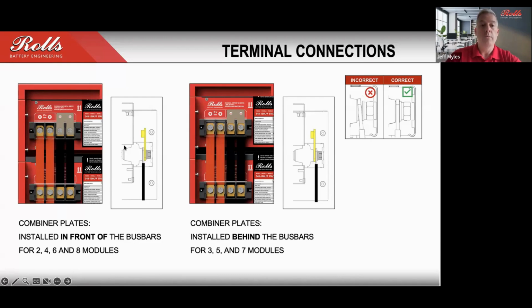There's an order in which you would connect these bus bars, and depending on whether you're assembling an even number of units or an odd number of units, the combination and the order of doing that is outlined in the manual. You're going to start with either the combiner plate in front of or behind the bus bars.